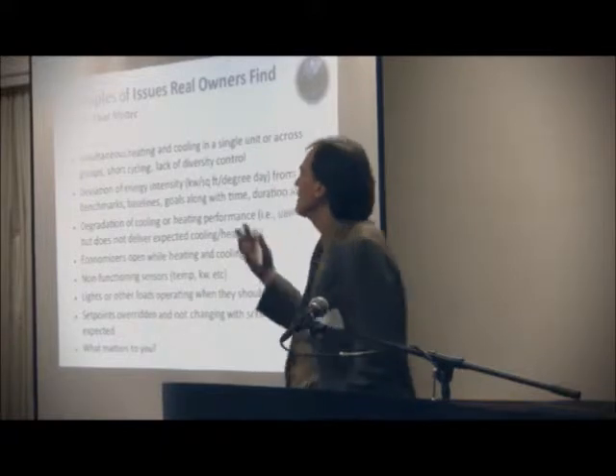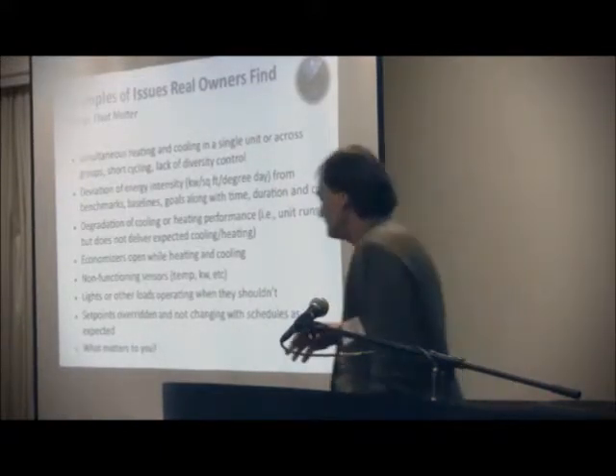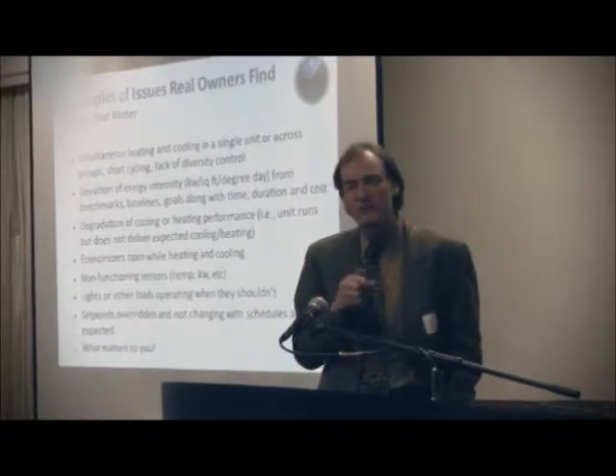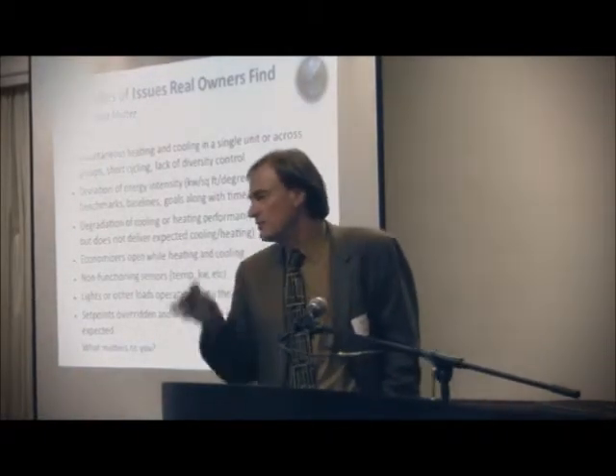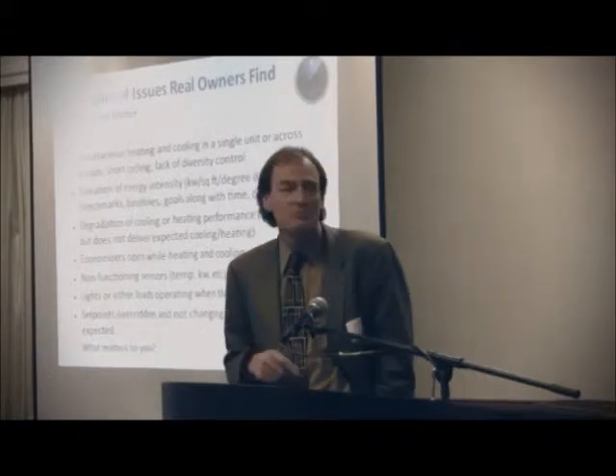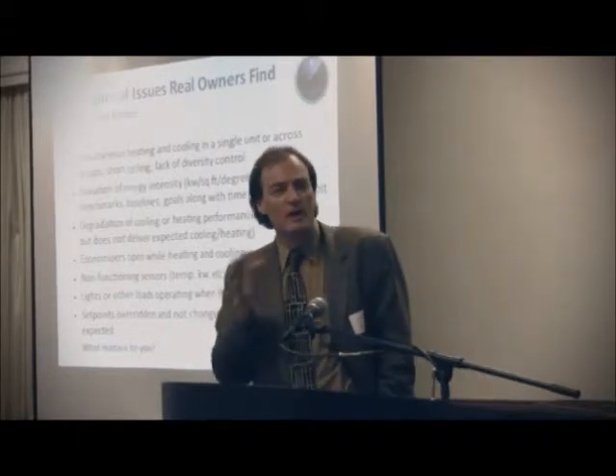Then there's equipment-oriented stuff—we call it fault detection, and it's very different from alarms. For example, what if we're no longer achieving adequate delta T temperature drop across a coil? We're keeping the space comfortable, but we're not getting the proper delta T.